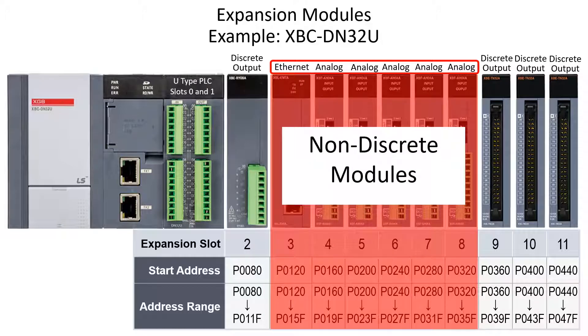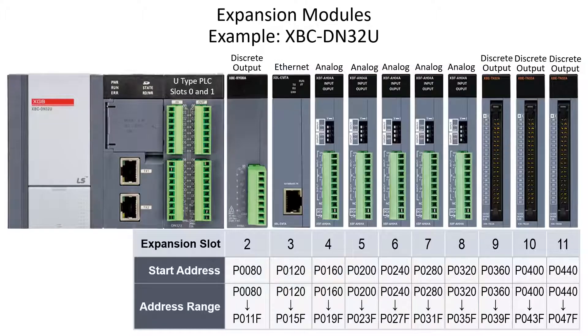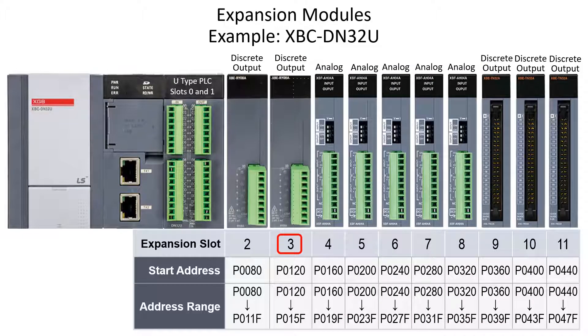Slots 3 through 8 are communication and analog modules. Although non-discrete modules, they are each allocated 64 bits of P data in the configuration. If the Ethernet module in slot 3 is replaced with a discrete output module, the P address range remains the same. The first discrete output in slot 3 will begin with the starting address of P 12 bit 0.